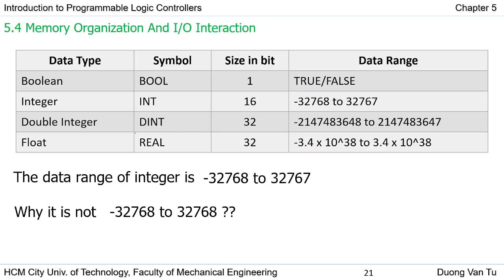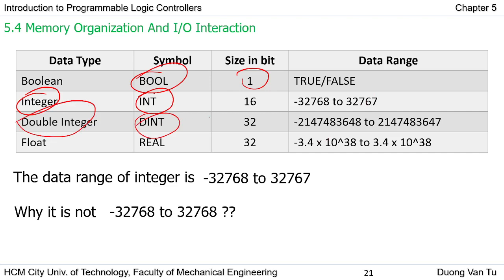Now we can see the data types in the PLC. There are four types of data or memory devices. First, Boolean: symbol BOOL, size 1 bit, data range is 0 or 1. Second, Integer: symbol INT, 16 bits, range from -32,768 to 32,767. Third, Double Integer: symbol DINT, 32 bits with corresponding range. Finally, Float or Real numbers: also 32 bits with a corresponding floating-point range.